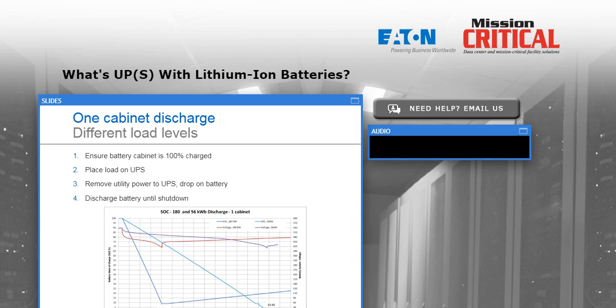Good performance, actually, for a single cabinet battery in this case. And then power is returned, and you see the red line continue to slowly increase as that battery recharges. Now, once the battery does recharge, we discharge it again, but now at only 56 kilowatts on that battery. This time we're following the blue line, and you see that it discharges very, very gradually over time. The cutoff voltage, the little V-shaped notch in the curve, is at the same point as it was on the red curve, about 410 volts DC on a 480-volt battery. But we're talking about 33.5 minutes of backup time at that lighter load.